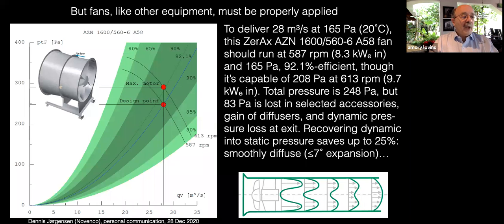But you have to apply the fan properly. In this application example, a ZerAx vane axial fan can be 92.1% efficient if it's run at exactly the right conditions, although it's 90%. Bullseye is actually quite a large zone. Moreover, up to 1/4 of the fan energy can be saved by using a carefully designed diffuser to regenerate dynamic pressure into static pressure that can then overcome duct friction, which of course you should first minimize with the duct equivalent of fat, short, straight pipes.